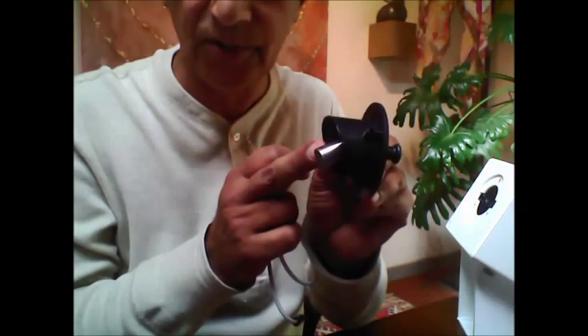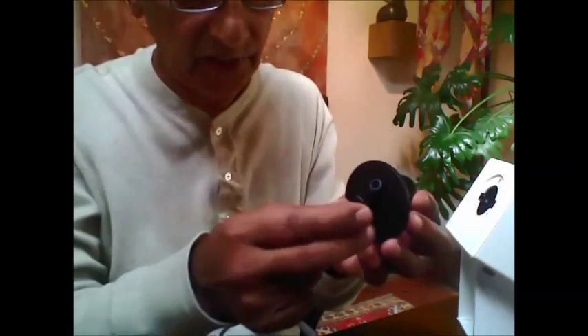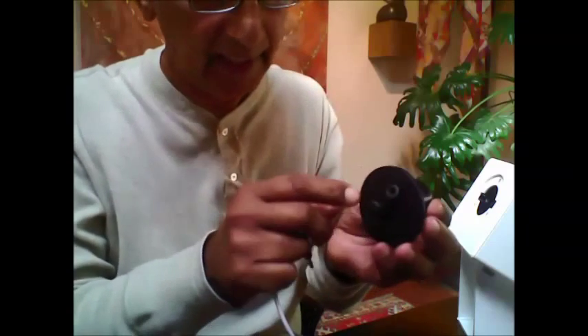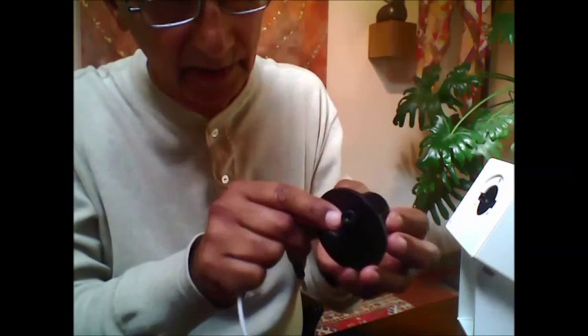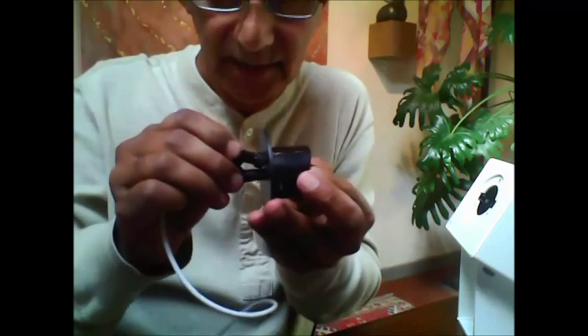This calibration unit is already provided inside the box. Here you see this is a titanium electrode — titanium being a very stable material provides a very optimal state for our calibration. On this side you have a handle to insert and pull out. And there is a small opening where we slip this white cord that we obtain. Hold the electrode in this manner — do not place your finger on the tip — and gently insert it.